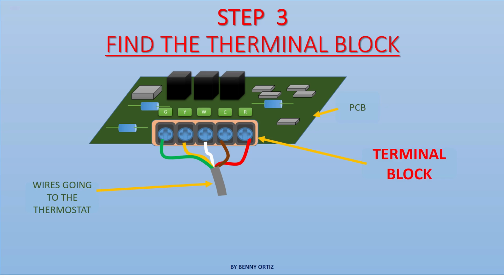For older HVAC systems, expect to see lots of wire nuts connecting the thermostat wires to the HVAC wires. In either case, the wires are color-coded. Many times, however, you will find the color of the wires do not follow the standard convention. So it is important to take a photo of the existing wire connections before starting to remove the wirings from the terminals or from the wire nuts. This way there is a reference in case it is needed for any reason.